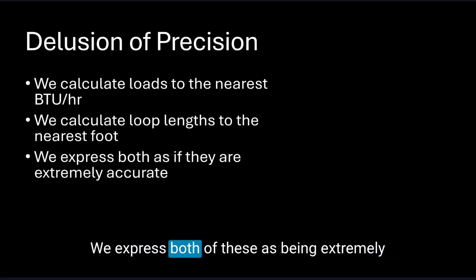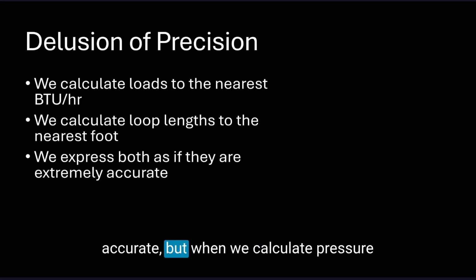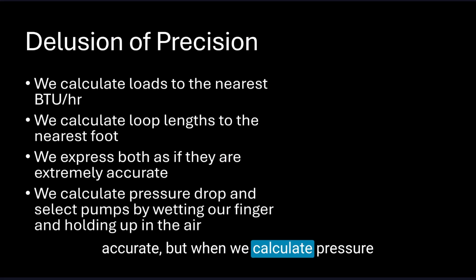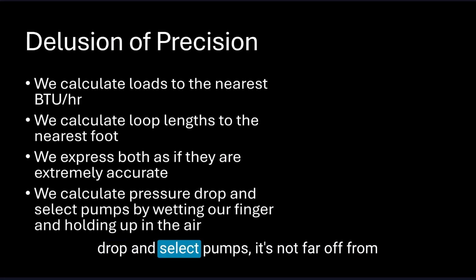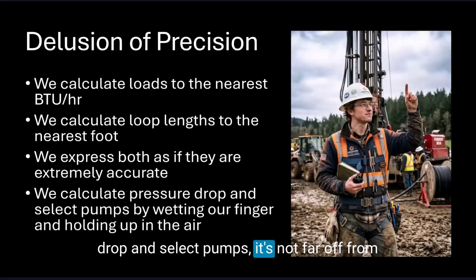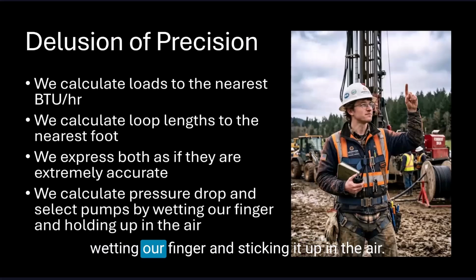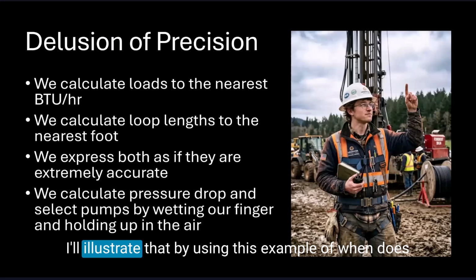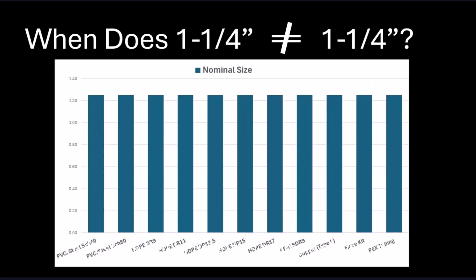We express both of these as being extremely accurate. But when we calculate pressure drop and select pumps, it's not far off from wetting our finger and sticking it up in the air. I'll illustrate that by using this example of when does 1 1/4 not equal 1 1/4.